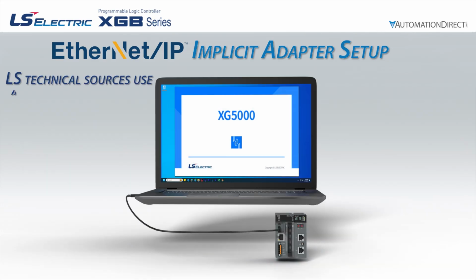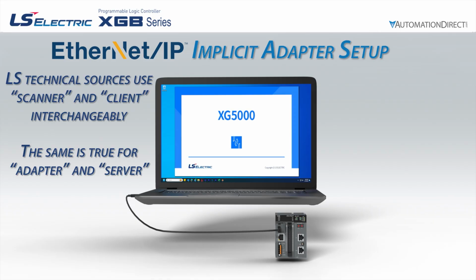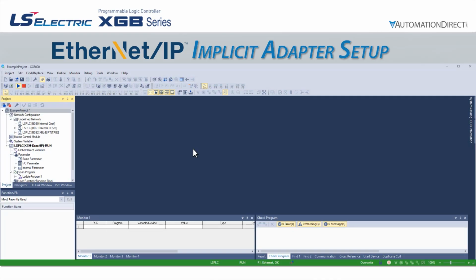It is important to note that the LS software and documentation may refer to the scanner as a client and the adapter as a server. Once we have the EtherNet/IP settings and the peer-to-peer connection configured, we can make the PLC available as an implicit adapter. To do this, we go to the project window on the left side of the screen and maximize the P2P03 subheading and double-click on EIP channel.